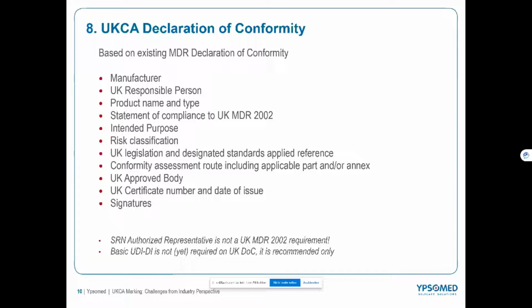We did this Declaration of Conformities based on our existing MDR Declaration of Conformities, so basically for us, it looks very, very similar. We included the manufacturer, the UK responsible person, the product name and type, statement of compliance to the UK MDR 2002, the intended purpose, the risk classification, the UK legislation and designated standards, applied references, of course, the conformity assessment route, the UK approved body, the UK certificate number and date of issue, and the signatures. These last two are still open because we did not get the UK certificate yet, so we did not sign our declaration of conformities. These are still in draft version under review.